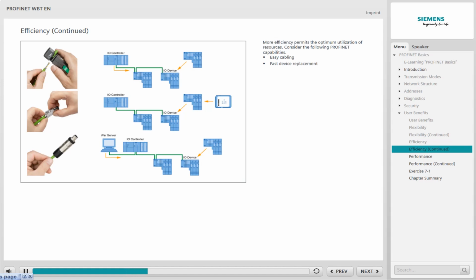No programming tools or engineering personnel are needed for replacing devices during servicing and maintenance. The downtime is reduced because only a new device from the warehouse must be used to put a machine or plant back into operation. PROFINET ensures that data is reliably transferred and unaffected by external sources of interference. Cable reflections and wiring problems, for example when a terminating resistor is missing, do not occur with PROFINET. Connection problems always affect 2 points and not an entire line. Errors can be located immediately. The use of PROFINET is also possible without any problems in EMI-sensitive areas.